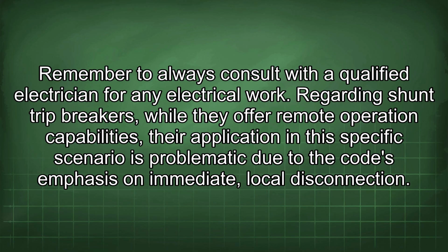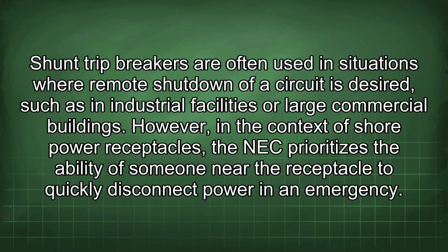Regarding shunt trip breakers, while they offer remote operation capabilities, their application in this specific scenario is problematic due to the code's emphasis on immediate, local disconnection. Shunt trip breakers are often used in situations where remote shutdown of a circuit is desired, such as in industrial facilities or large commercial buildings. However, in the context of shore power receptacles, the NEC prioritizes the ability of someone near the receptacle to quickly disconnect power in an emergency.